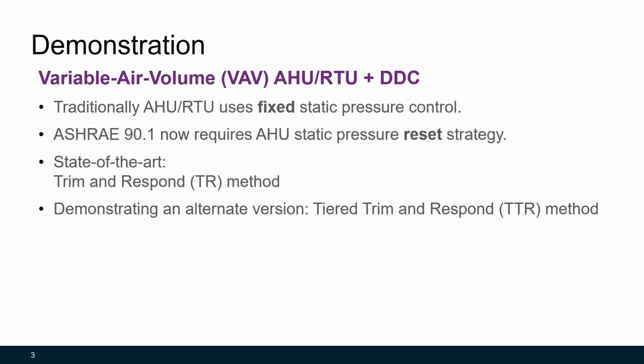This project is about demonstrating advanced control strategies to reduce fan energy. This advanced control is applicable to variable air volume systems, air handling units, and rooftop units with direct digital controls. Traditionally, an air handling unit or rooftop unit uses fixed static pressure control, but ASHRAE 90.1 now requires air handling unit static pressure to be reset through the trim and respond method. This project is demonstrating the tiered trim and respond method compared with this fixed static pressure control.